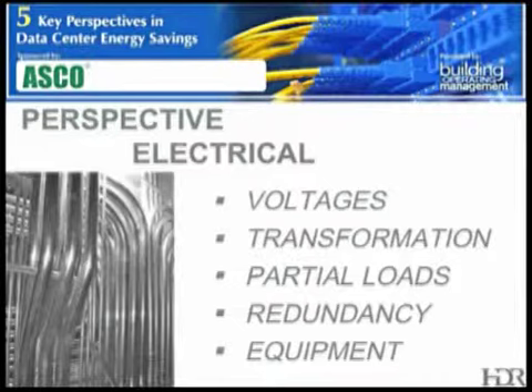Try to reduce the amount of transformation that you have in series. So if you can stay at the higher voltage, then you'll reduce some of that transformation. Look at transformer-less UPSs. One of the things that you need to be careful of, though, as we drive to eliminate the transformation and operate the facility at the native facility entrance voltage, we do that to save both on the electrical losses and the price of the transformer. But when we lose that transformer, we also increase the harmonic currents that are available, and now we may need a neutral conductor upstream, where before, if we had a 3-wire feeding that delta system, we didn't have that neutral. So it's important before you go to a system like that to take all those considerations into effect.